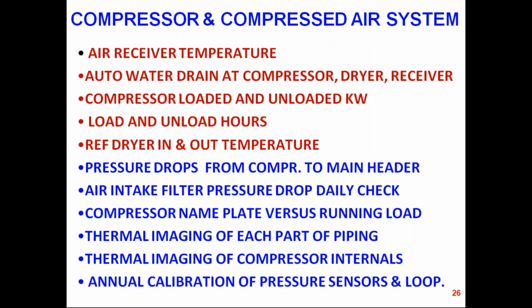This condition monitoring, as an energy auditor, we can definitely do not only on the compressor, it can be done on any utility. Once you monitor the air receiver temperature, this should show the compressor is healthy. Compressor is an area of concentration compared to any other production machines, because the air intake is taken from the outside. If the air intake variation in temperature and RH is there, that will definitely affect the compressor performance. The air receiver temperature should not be more than 5 degrees centigrade above the ambient temperature around. If it is going more, that shows the post air cooler is not healthy.